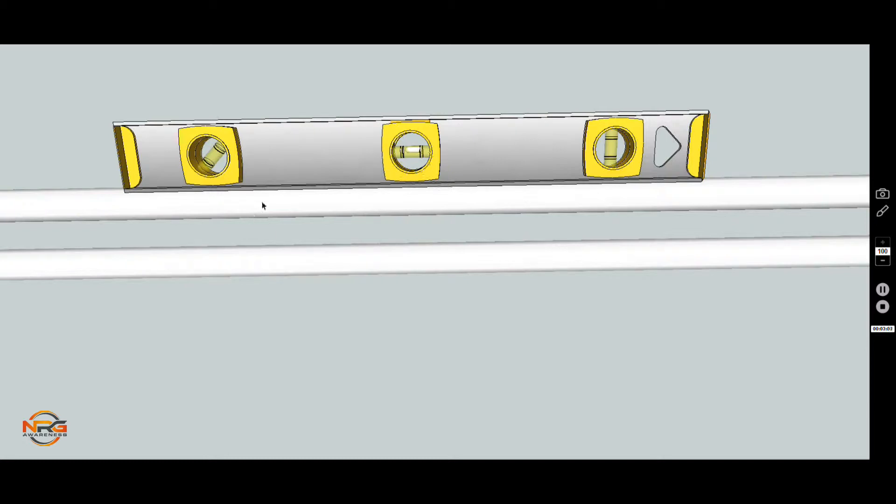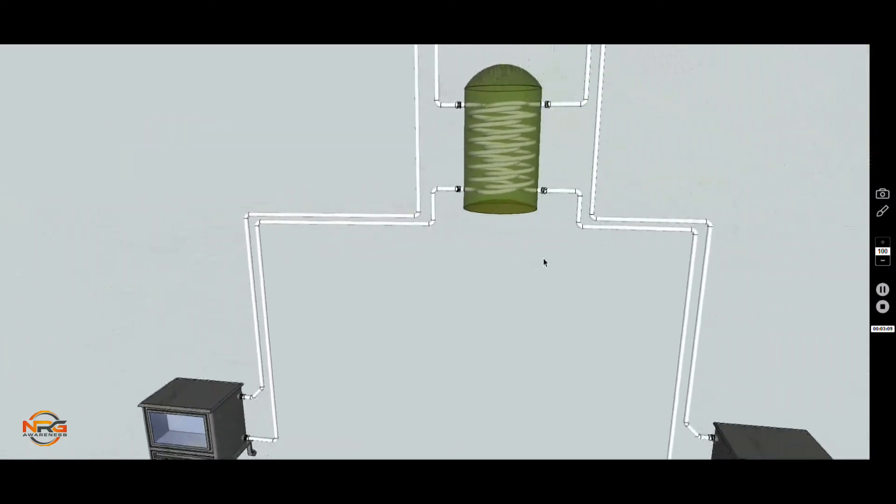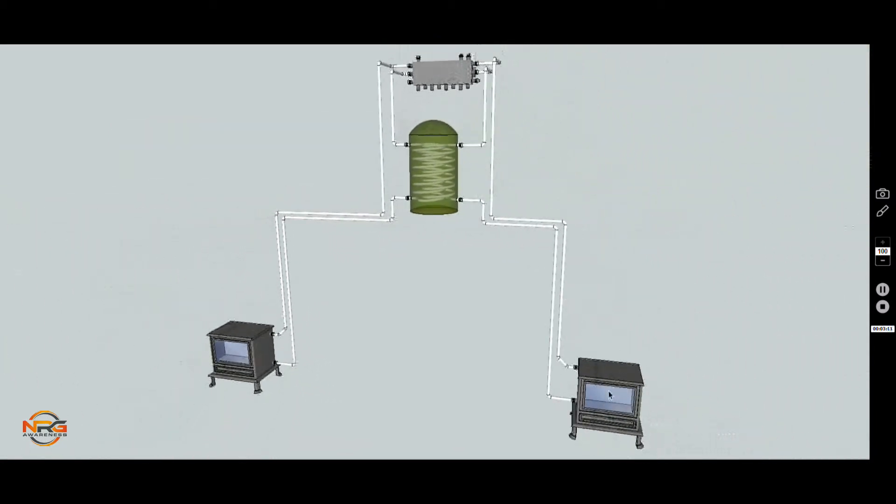If we introduce a stove on the other side, exactly the same situation occurs. Rise as quickly as possible up into horizontal pipework, and then on any horizontal run, again have it rising towards the high point to vent any air in the system and also cause the thermosiphon to work properly.